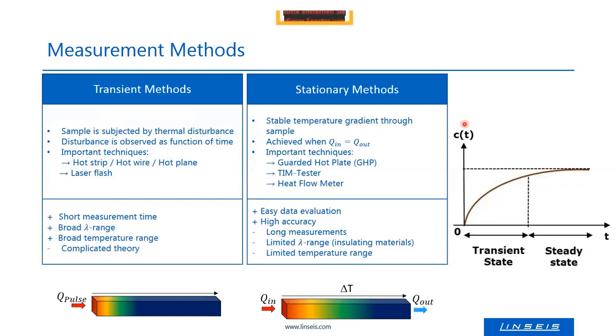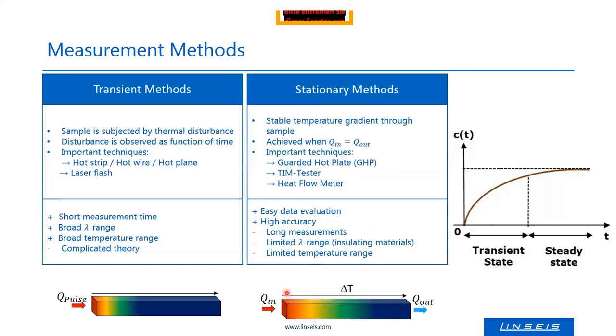When thermal conductivity needs to be measured, in principle there are two different methods. The older one is the stationary method. For many years, thermal conductivity was measured with plate instruments. The working principle is that you have a sample with a hotter plate on one side and a colder plate on the other, and you wait until you have a constant temperature gradient within the sample. The heat flux is measured, and from the heat flux and the delta T, the thermal conductivity can be easily calculated.